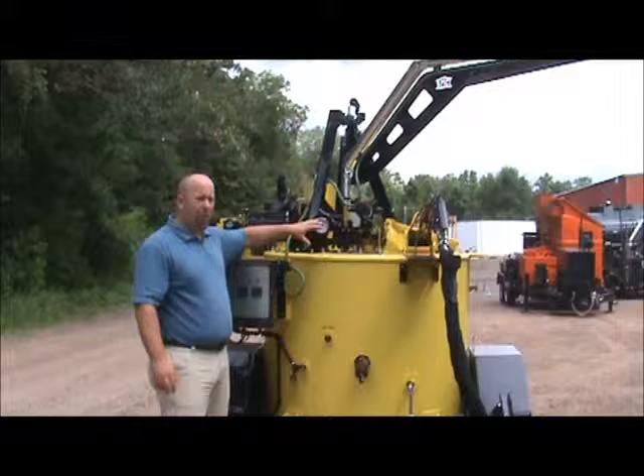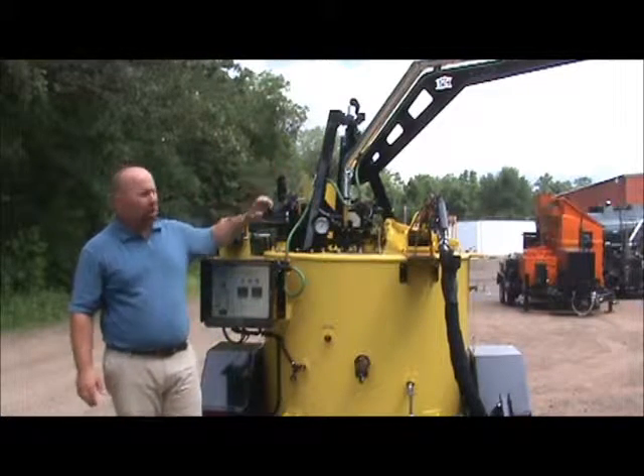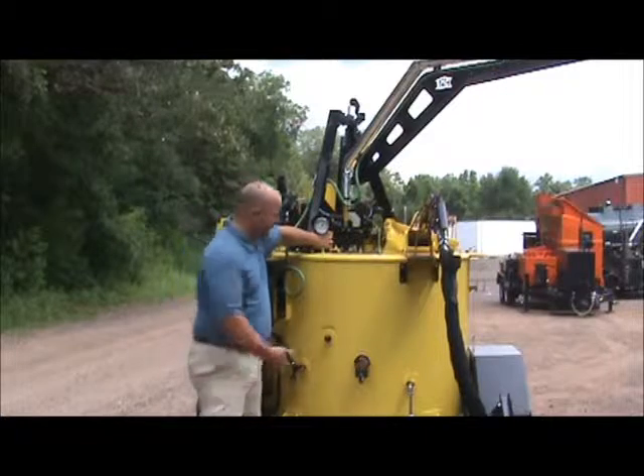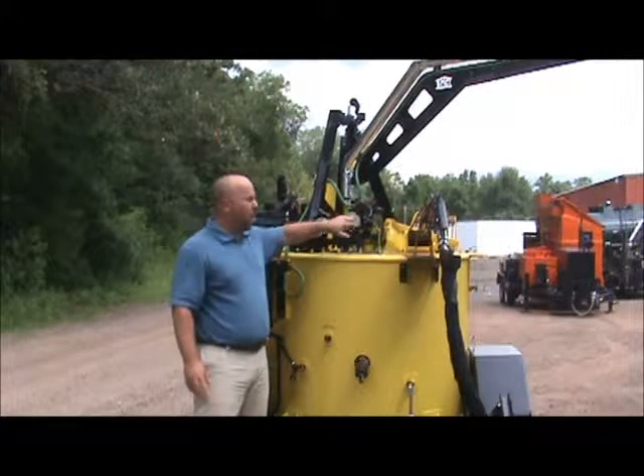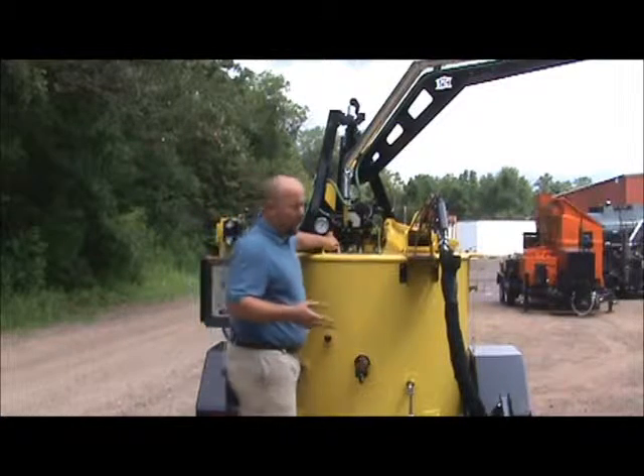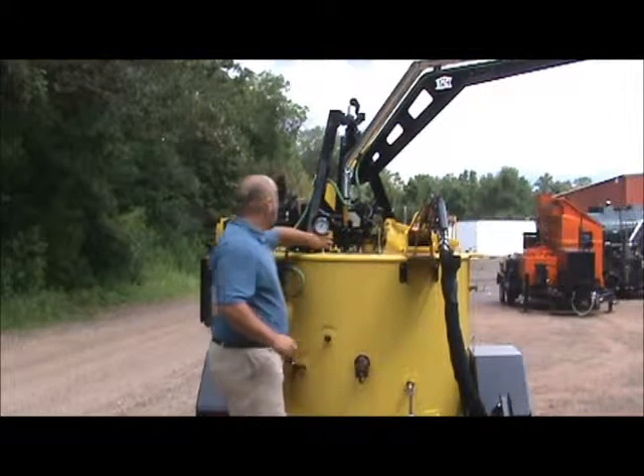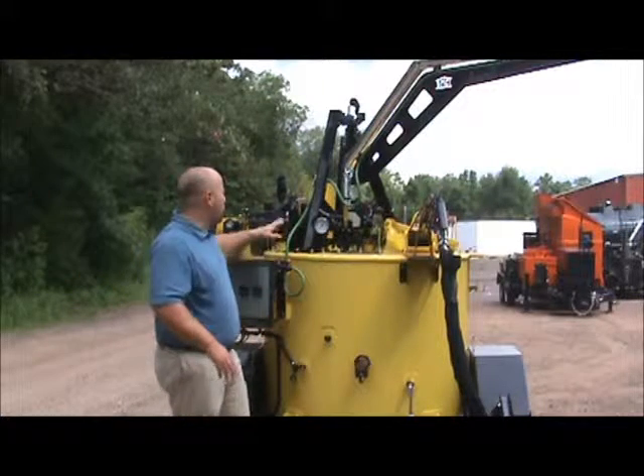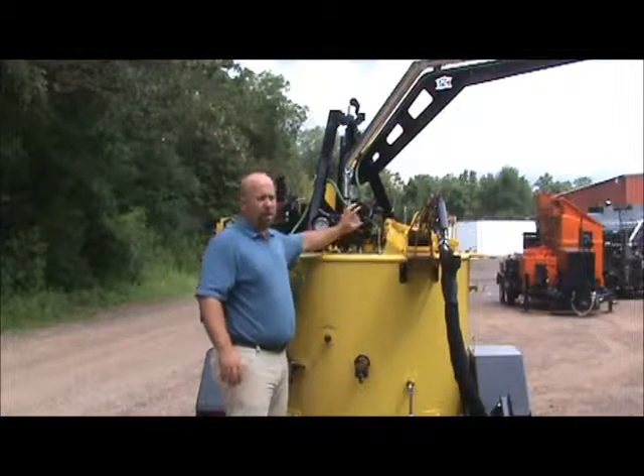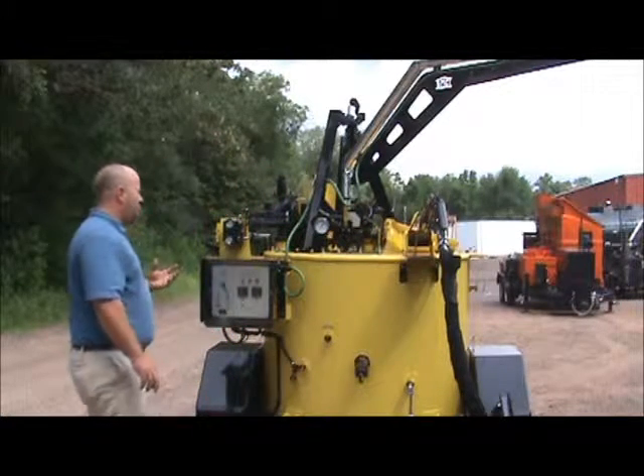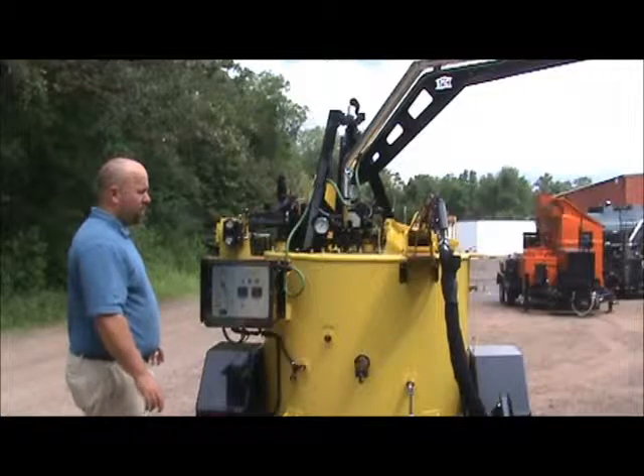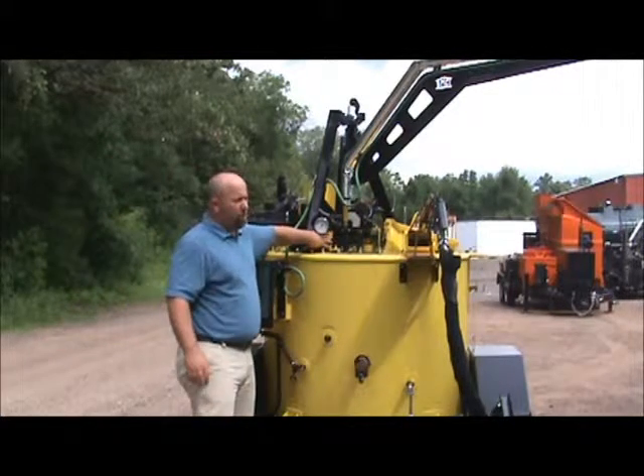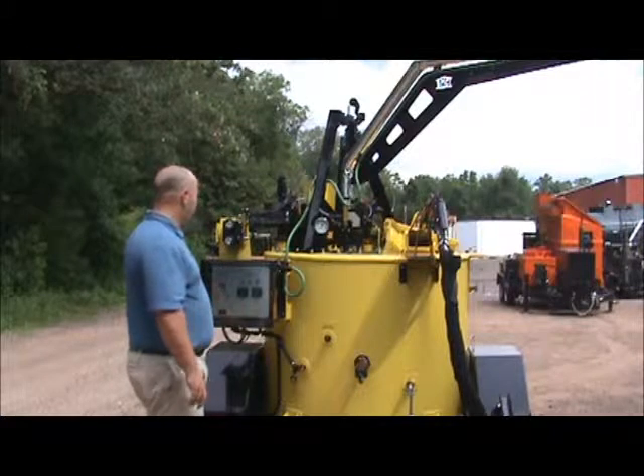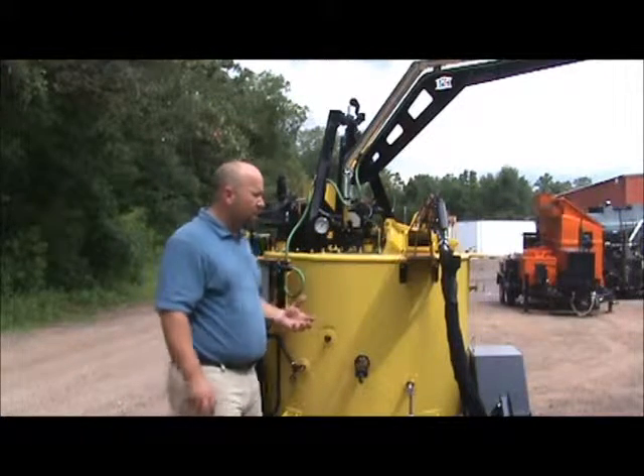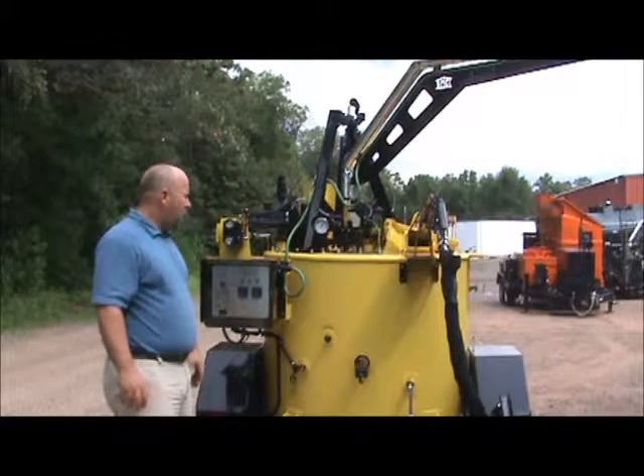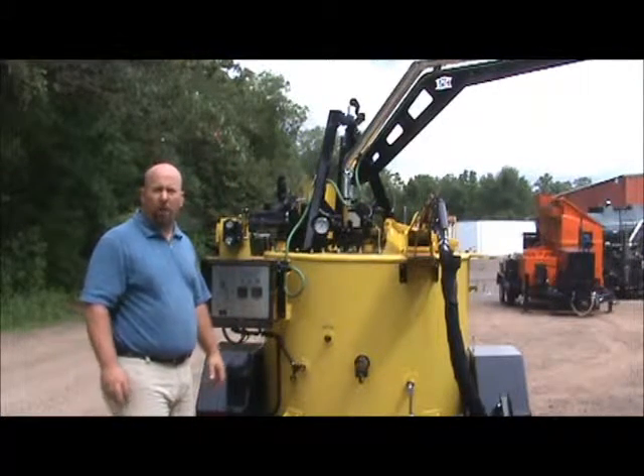If you forget to do that, or if someone walks up and turns the key off while everything's running, you're going to have plumbing that's plugged up because it's not inside the tank where it's hot and it doesn't have a heater in it. If that happens, and sooner or later someone will forget to do that, you do have to warm this portion of the plumbing up with a hand torch. You have to be very careful because we've got wiring, and you can melt the guts out of the valve. So in the event that they forget to reverse the pump, you have to get a torch on the plumbing to thaw that out. But as long as you reverse the pump for 60 seconds to 3 minutes, you're not going to have problems tomorrow morning.